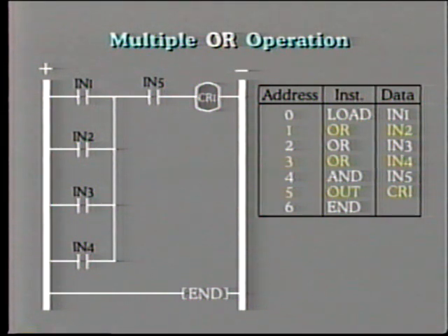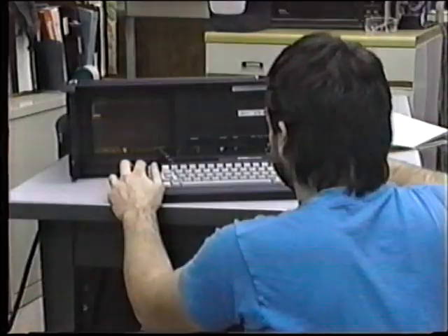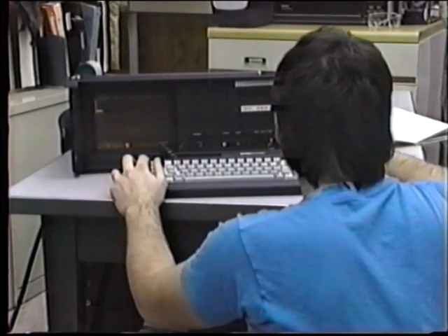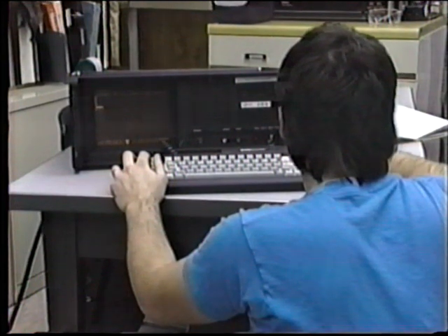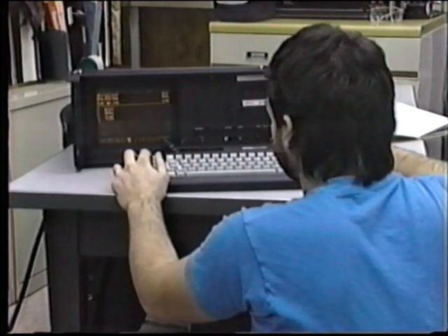The instructions entered into the program for each address would look like this. Input contact IN1 must be loaded, that is, closed, or contacts IN2 or IN3 or IN4 and contact IN5 in order for an output signal to energize the control relay. Nowadays, many PLC programmers allow us to build up a logic diagram from the keyboard instead of using symbols for written instructions. In this method, we simply select the appropriate address and then add contacts and other functions as we move across each rung of the ladder.